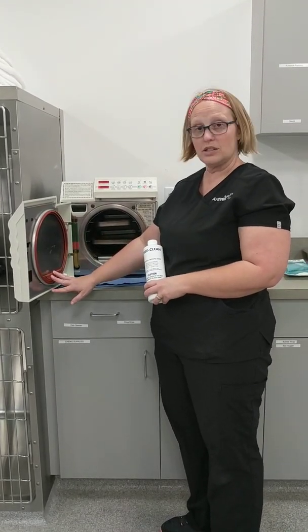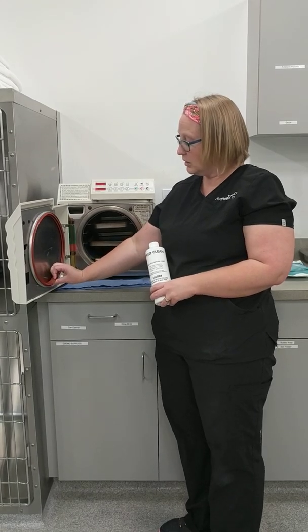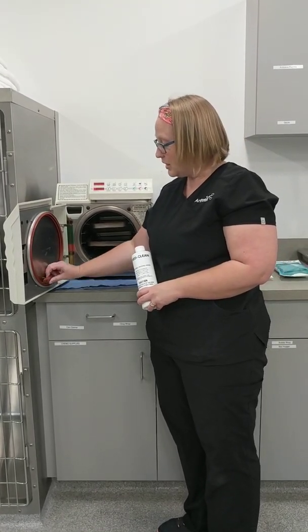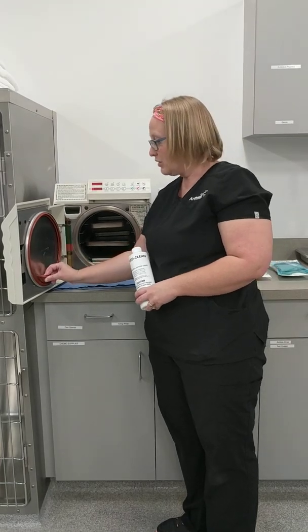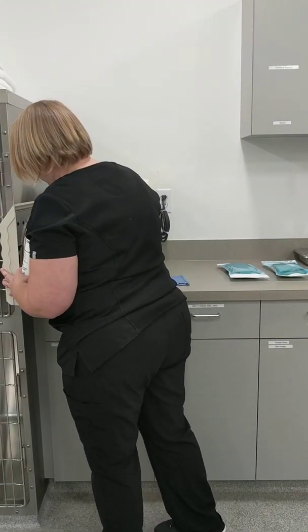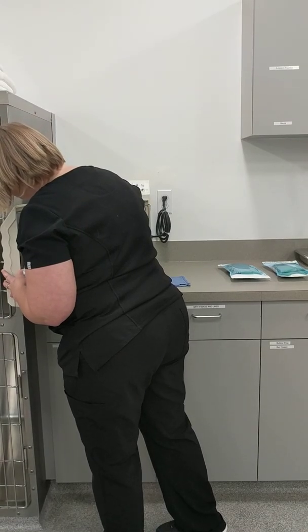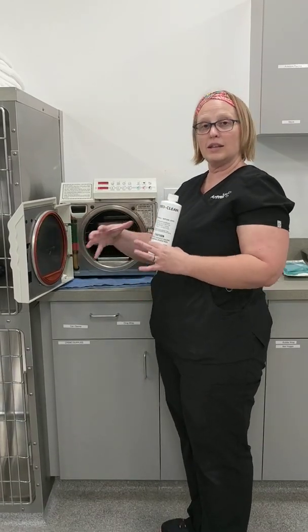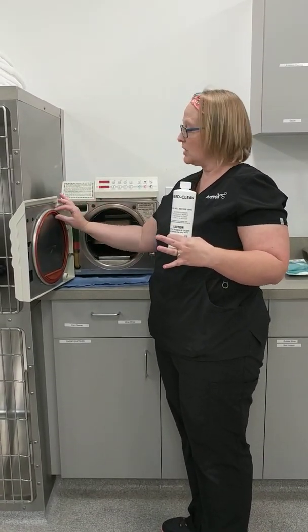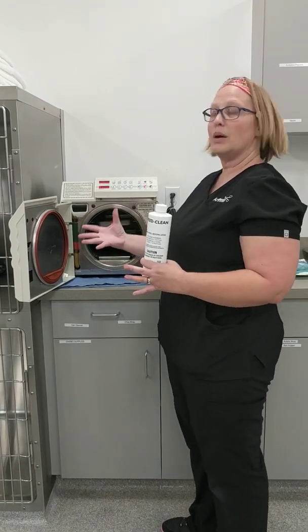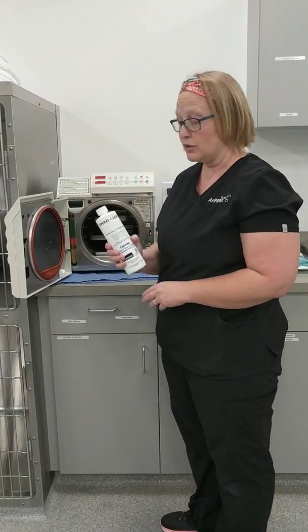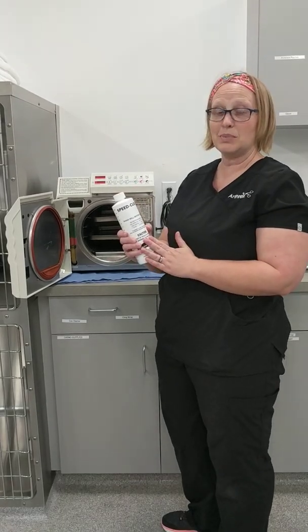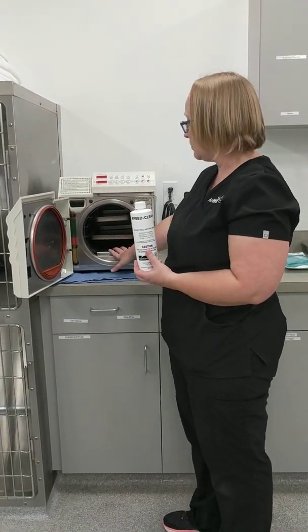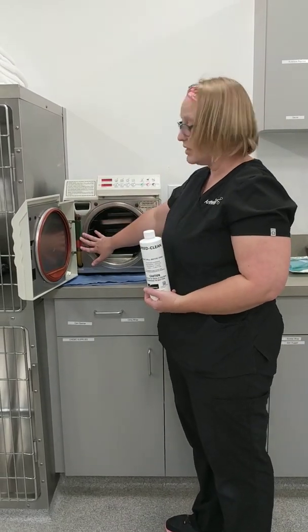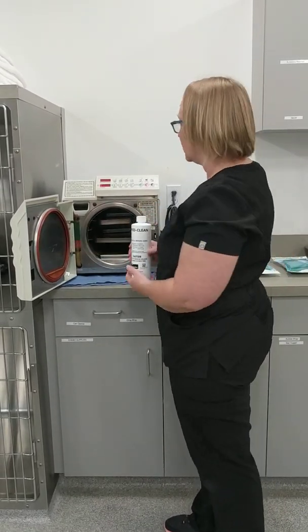Another part of the autoclave that always has to be checked is your seal. This rubber seal holds all of that steam and everything in. This lining right here gets worn out. There are replacement parts. I'm going to put that back in after I pulled that to show you. And this rubber O-ring here, it has a wire bar that expands and then pushes that and then makes that seal nice and tight here. That way you don't get steam burned and things like that as the autoclave is running. Again, Speed Clean is a fabulous product that allows you to wipe the inside metal portions of your autoclave. It also cleans out all of your water portions, again, distilled water only.